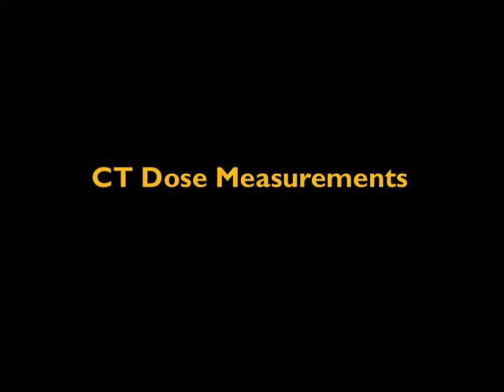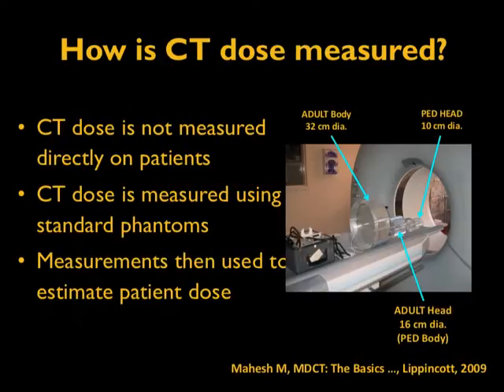Having that background, I want to discuss some basic physics of CT dose measurement. When discussing CT dose measurement, it is imperative to start with how CT dose is measured. The first caveat is that CT dose is not measured directly on patients. Even though we express CT dose to patients, all measurements are done using standard phantoms. Medical physicists use standard phantoms, measuring dose on the phantoms and then extrapolating to explain CT dose to the patient. Those measurements are then used to estimate the patient dose.